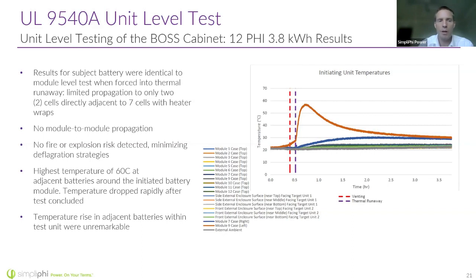As this test was being run, there was no fire or explosion detected outside of the batteries, right? So there was no big fire, even though we're trying to force a fire to happen. There was no module to module propagation. That means that even though we forced battery 8 to off-gas, we forced it to go through a thermal runaway by actually placing heaters inside it, batteries number 9 and number 7 right next to it did not go into thermal runaway themselves, right?